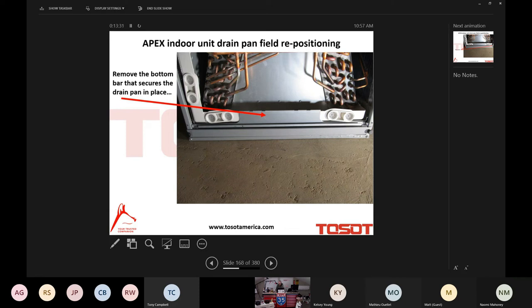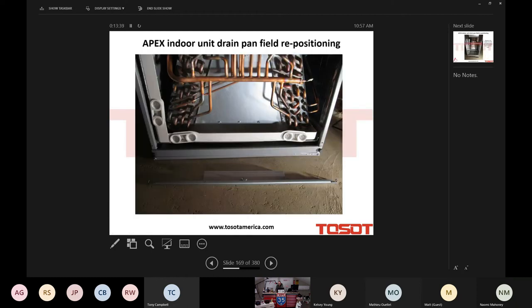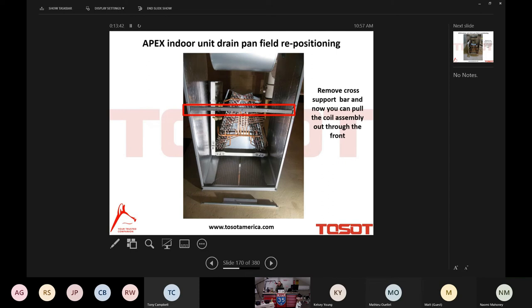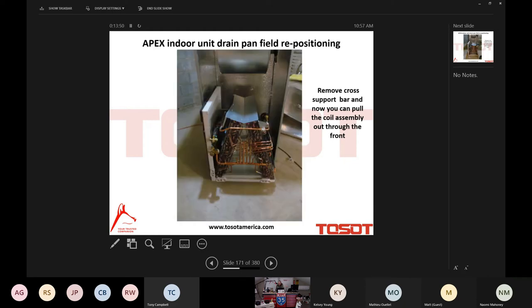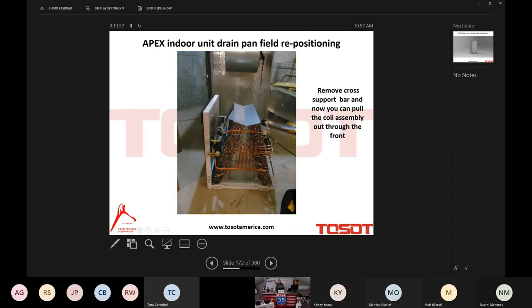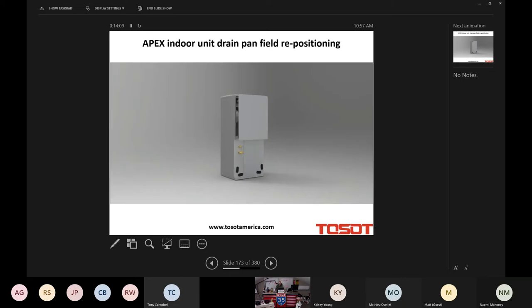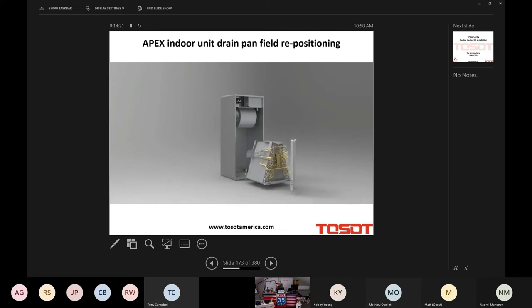But if we want to change the position of that horizontal pan, we need to remove that bottom brace. It's just two screws, and that comes off, simple and easy. And then the last is what I'll call a horizontal brace at the midpoint of the cabinet. Remove that, and that gives you the ability to do this. That is literally to pull the coil forward, and now you can change that horizontal pan from left to right to have a return inlet right, supply outlet left. And again, this is what you are doing out in the field. Very, very simple. Very, very nice design by Tosot, so that this is field convertible depending upon the horizontal position that the customer wants to use.